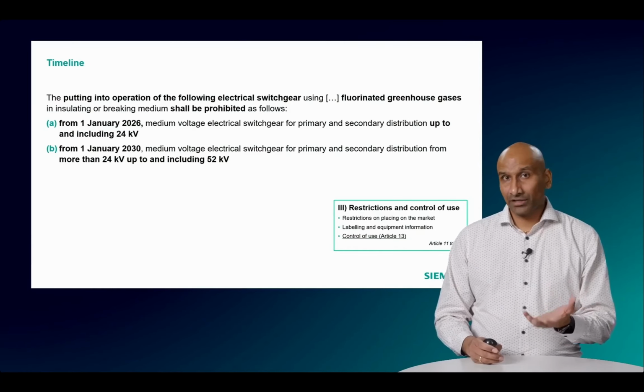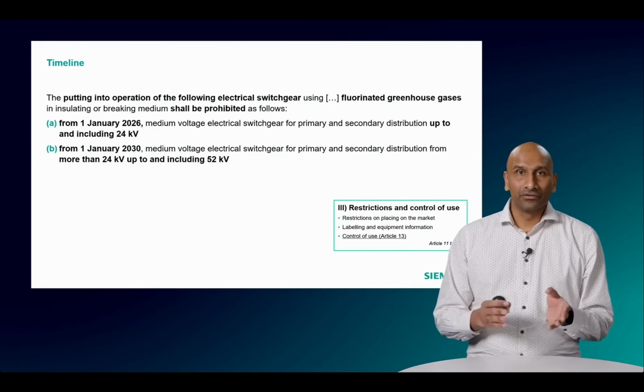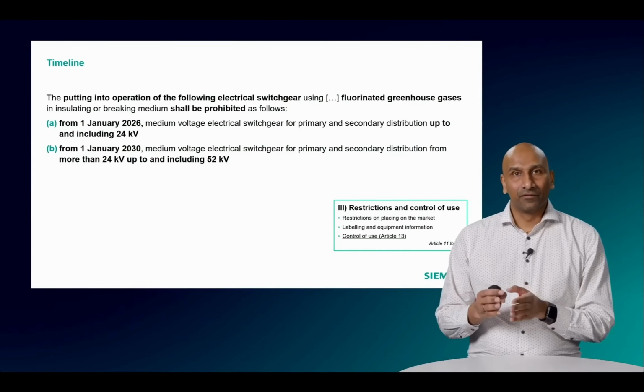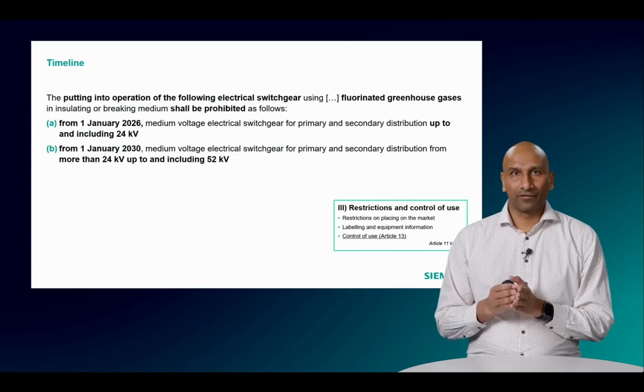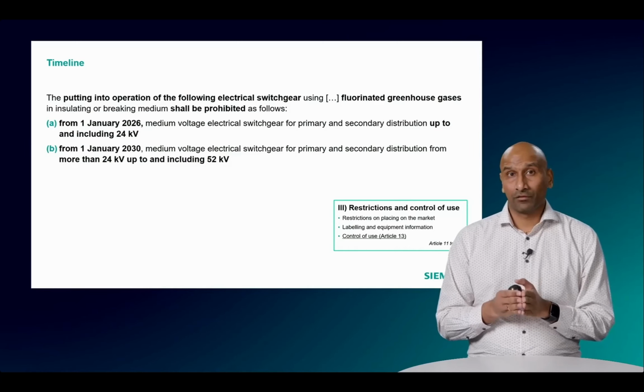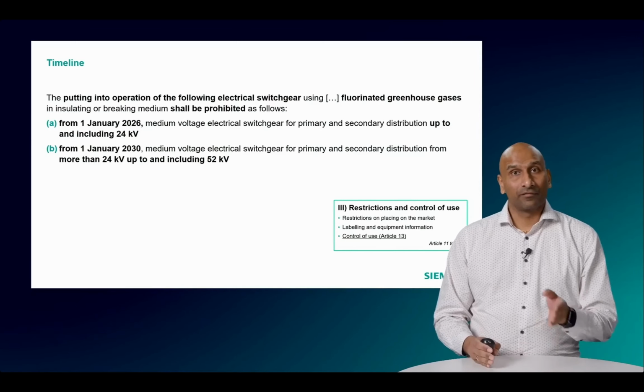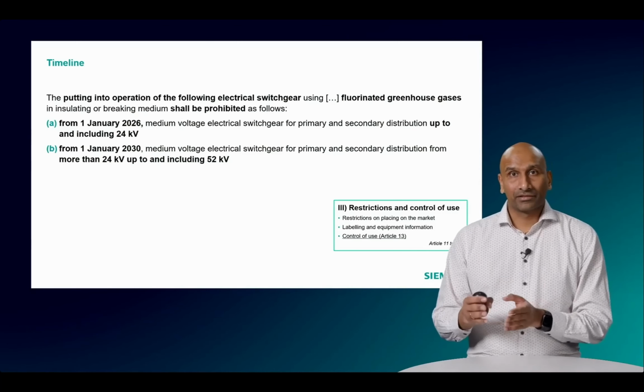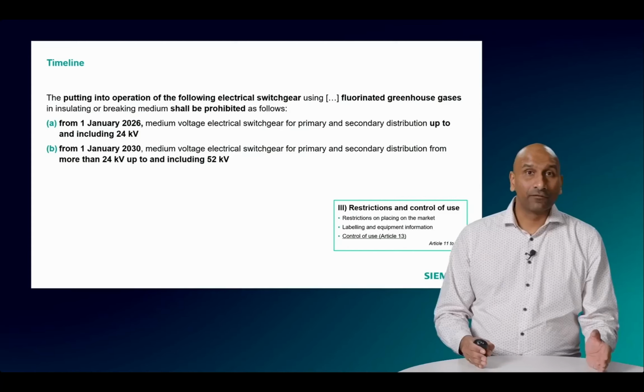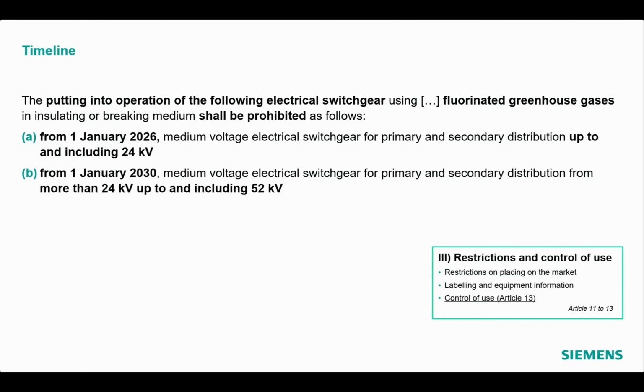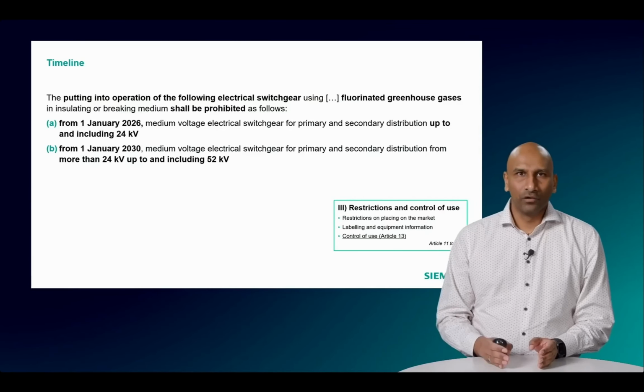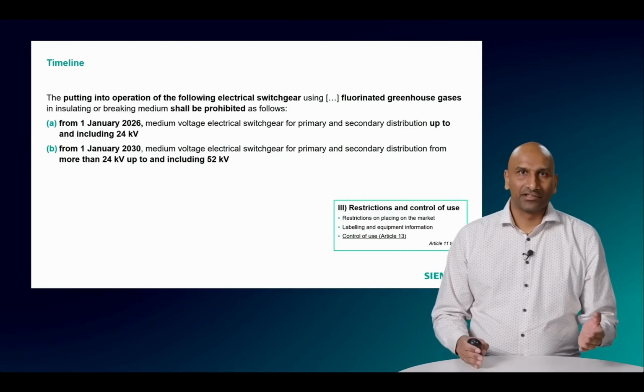From 1st of January 2026, which is not so long away from now, the use of F-gases in medium voltage switchgear for primary and secondary distribution up to 24 kV will be completely prohibited. And from 1st of January 2030, this ban extends to switchgear for the ratings between 24 kV and 52 kV. It's important to know that the critical date for compliance is the putting into operation date, not the purchase or the delivery date. This means any switchgear installed beyond these deadlines must be fully F-gas free, which accelerates the transition towards sustainable alternatives.